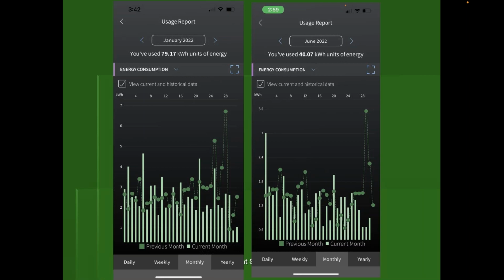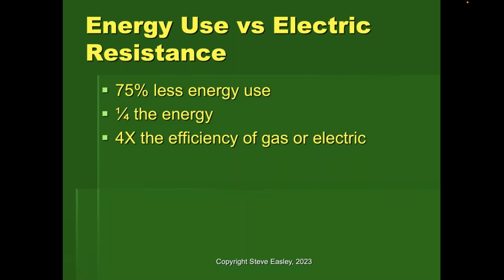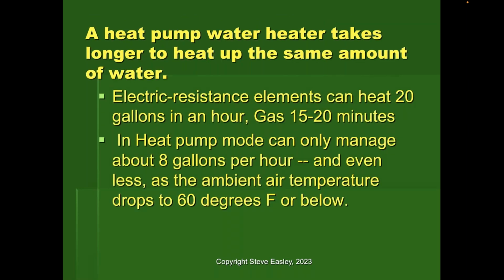So heat pump water heaters are a lot more energy efficient. Again, 75% less energy use, or a quarter of the energy you were using, 4 times the efficiency of gas or electric. Okay, now a couple things to note. Electric resistance elements can heat about 20 gallons in an hour. Gas can do it in about 15 to 20 minutes. So again, fossil fuels have the ability to liberate a lot of heat in a short period of time. The bad news is it's not quite as good for the environment. When a heat pump water heater is in heat pump mode, it can typically average about 8 gallons per hour, and even less if the temperature where the water heater is located is below 60 degrees.